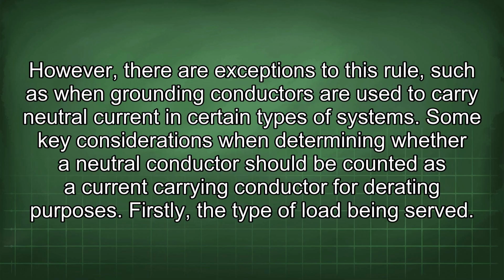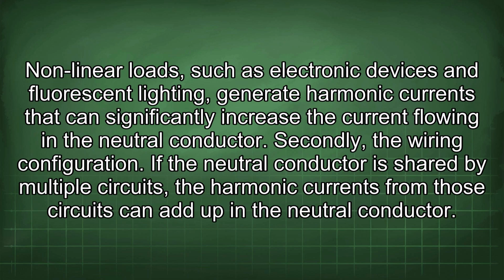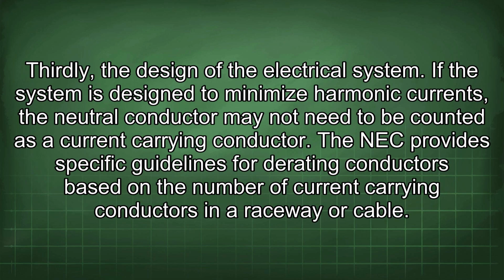Some key considerations when determining whether a neutral conductor should be counted as a current-carrying conductor for derating purposes. Firstly, the type of load being served. Nonlinear loads, such as electronic devices and fluorescent lighting, generate harmonic currents that can significantly increase the current flowing in the neutral conductor. Secondly, the wiring configuration. If the neutral conductor is shared by multiple circuits, the harmonic currents from those circuits can add up in the neutral conductor. Thirdly, the design of the electrical system. If the system is designed to minimize harmonic currents, the neutral conductor may not need to be counted as a current-carrying conductor.